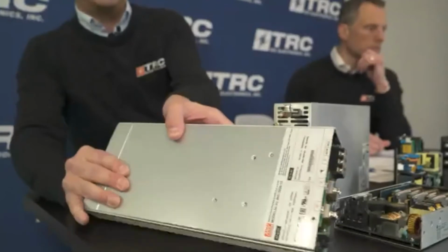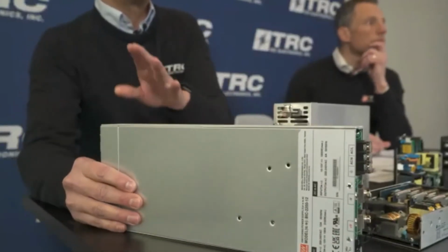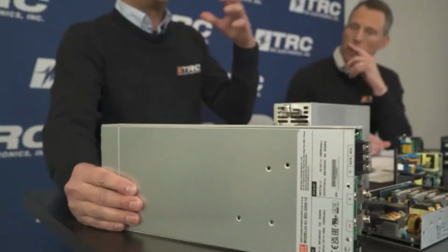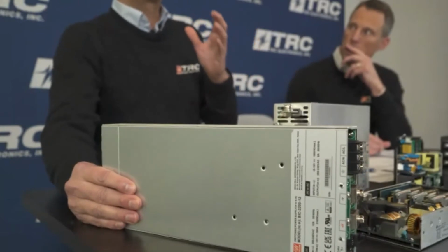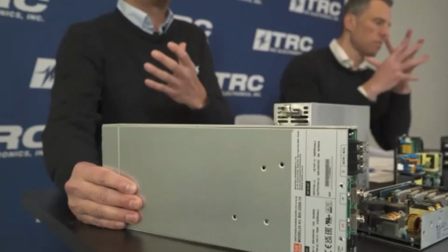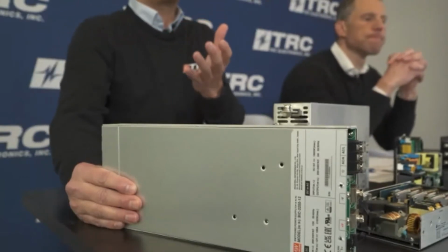This product is able to take in AC input from the grid and supply a DC output to charge batteries. Once those batteries are charged, you have to discharge them to cycle them. So this product takes the battery voltage you just charged and converts it back to AC power, using the grid as the load to discharge those batteries. Essentially, you're recycling that energy.